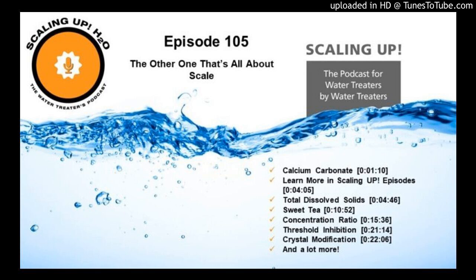So whatever one you're comfortable using, that's the one that you're going to use, but they all do the same thing. They start with the saturation pH, and that is exactly what I said before. That means we are neither precipitating nor dissolving calcium carbonate. It is in equilibrium. With that, then one of those scaling indices will then put their spin on it, and they will say how scaling or how non-scaling the water is.